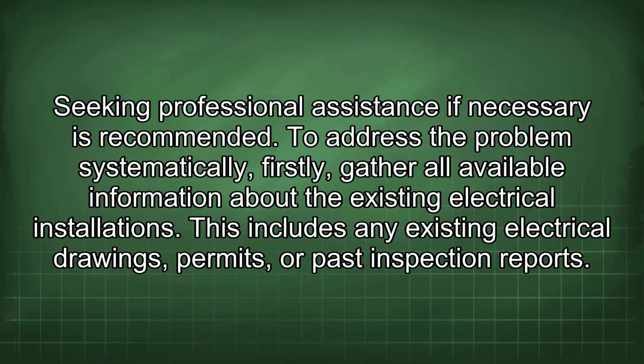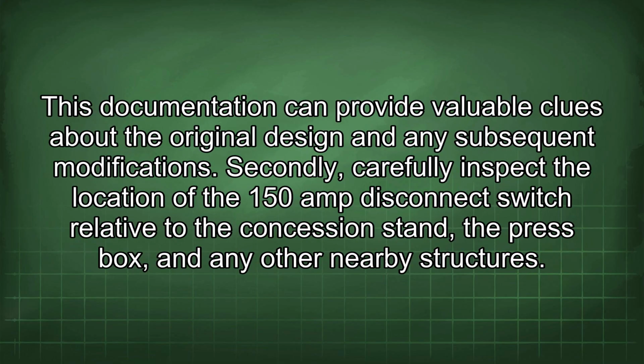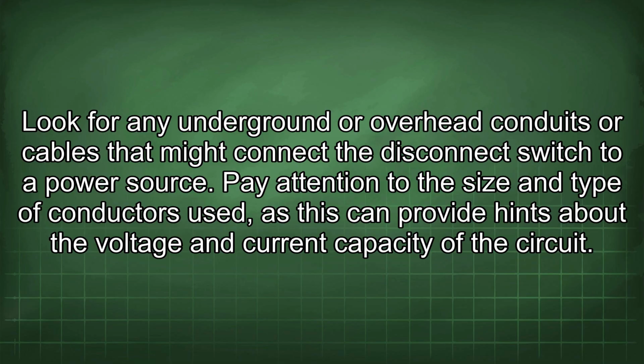To address the problem systematically, firstly, gather all available information about the existing electrical installations. This includes any existing electrical drawings, permits, or past inspection reports. This documentation can provide valuable clues about the original design and any subsequent modifications. Secondly, carefully inspect the location of the 150 amp disconnect switch relative to the concession stand, the press box, and any other nearby structures. Look for any underground or overhead conduits or cables that might connect the disconnect switch to a power source. Pay attention to the size and type of conductors used, as this can provide hints about the voltage and current capacity of the circuit.